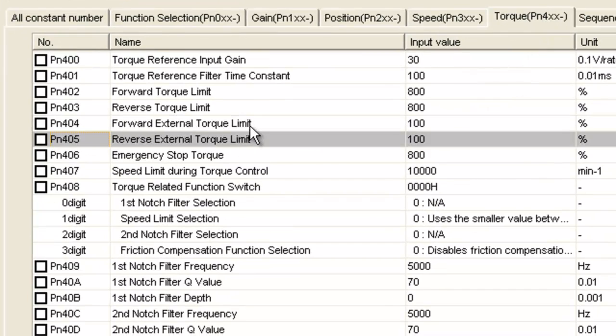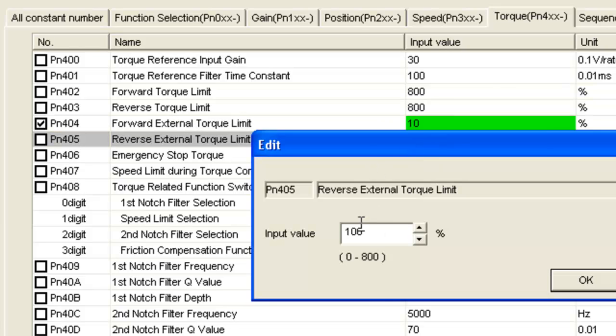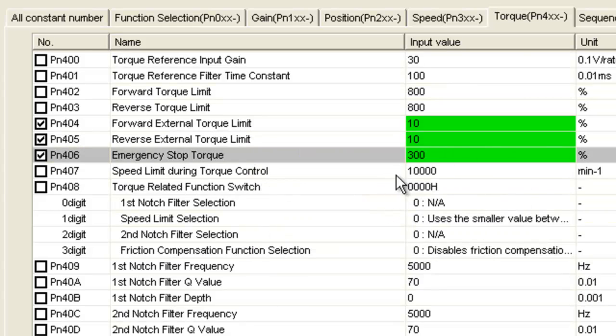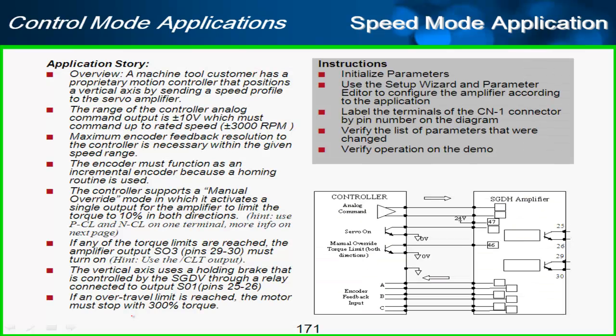The torque parameters associated with PCL and NCL are the forward and reverse external torque limits. I'll set those to 10 for forward and 10 for reverse. Right below that is the emergency stop torque, which I'll set to 300% — that's pretty much full stopping torque. I can write those over with no power cycle required.